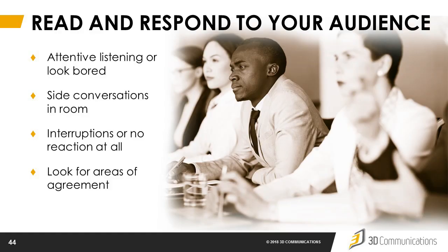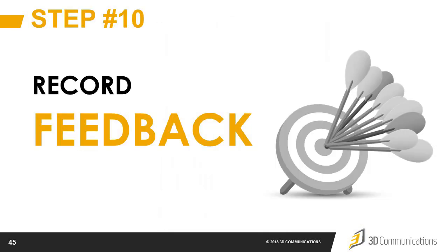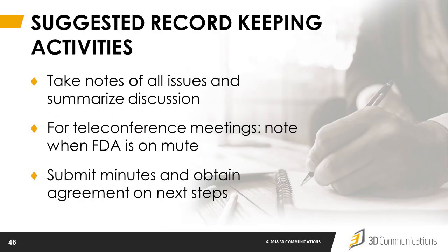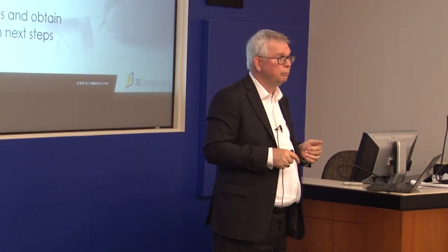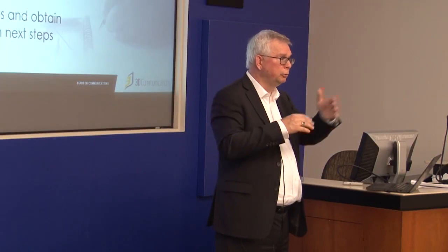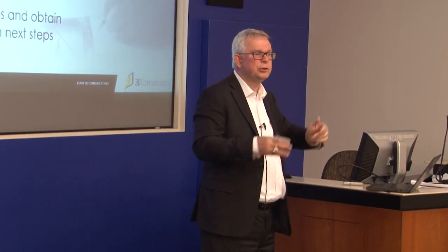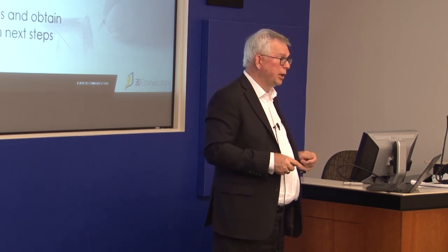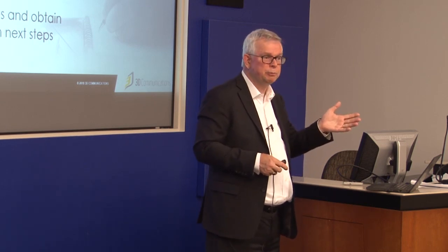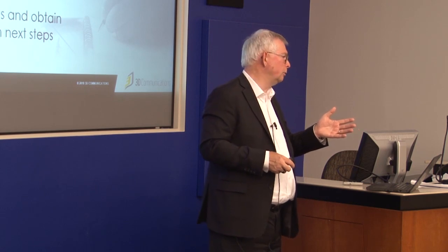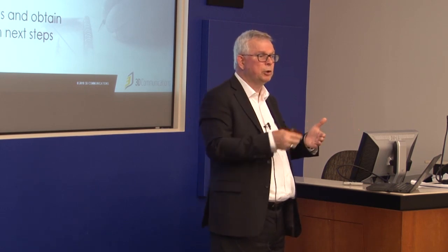This is a bit more of what I already told. Record feedback. So during the meetings, it's very usual to take notes. Most of the time the FDA asks you to summarize it. You send the minutes to them. Then they revise it, and that's then the official minutes that they give out. Rarely I've seen that the FDA gives you a full set of minutes already before you even send it to them. But they have to do it within 30 days, all those minutes. So we always advise to give those minutes pretty quickly.